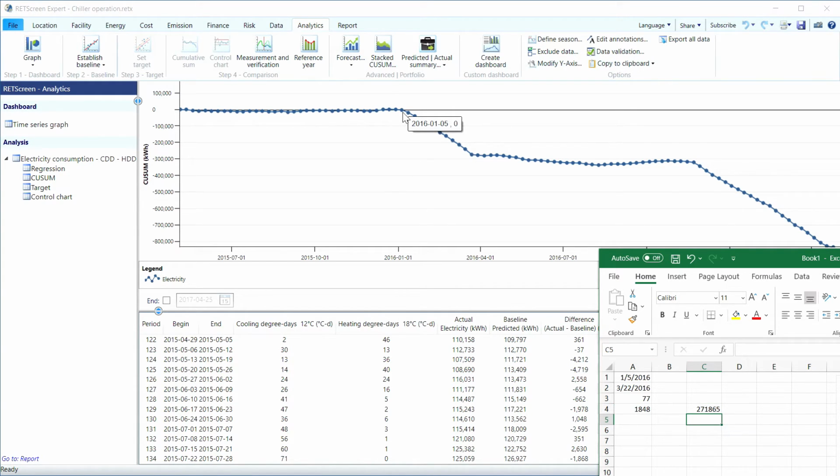So that's with the chiller being turned off. So basically we're saying when we turn off the chiller, it's the equivalent, I'll just take this kilowatt hours, divide by the number of hours, get 147 kilowatts effectively. And that's just based on a regression equation in a CUSUM.